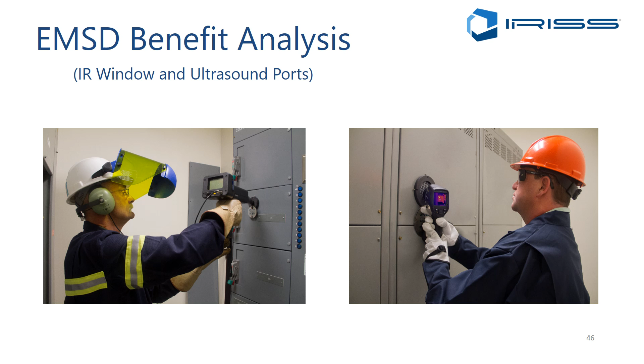One electrician shouldn't manhandle a panel when energized. Really, you don't want to be opening an energized compartment anyway. But if you are, it's not done by one person. You need a couple of pairs of hands on that, because the last thing you want to do is drop a panel into an energized piece of equipment, because that's when significant accidents happen.